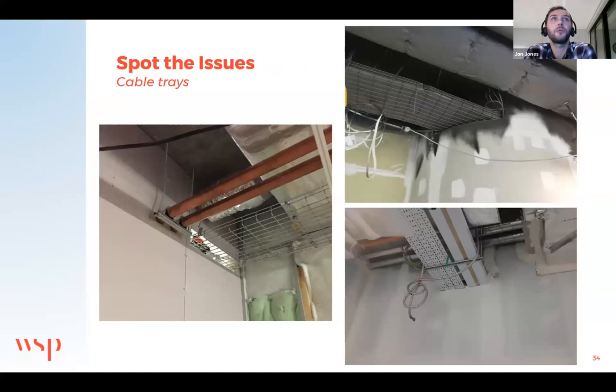Now, there's a few slides here which are spot the difference. So it's not a very interactive session, unfortunately, but I'll give you a second to have a look through those and see if you can spot the issues in terms of the acoustics with these images. And not to dwell on it too long, but again, cable tray here, you can see light straight through there. That's going to be bad acoustically. If you've got noise in, say, a plant room here, it's going to transfer straight out of there very easily.